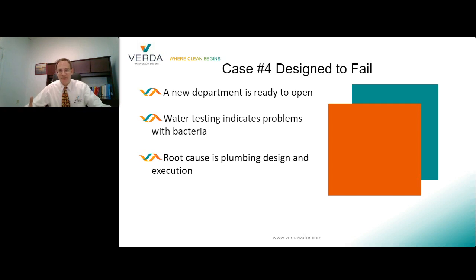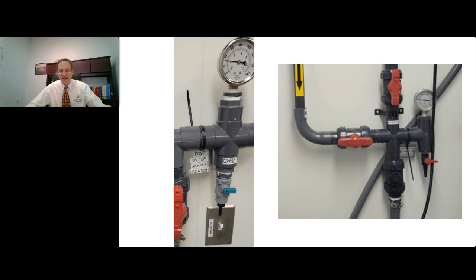Let me flip into that. You can see this on the second image to the right. The water's flowing, but this sampling port on the right-hand side isn't in the flow path, the water is stagnant there. This other sampling port is better, but still has a bit of a dead leg of stagnant water. What I find more offensive is they put the sampling port right next to the light switch, so anytime someone goes into the room to flip the switch, there's a good chance they'll touch the sampling port with their finger.